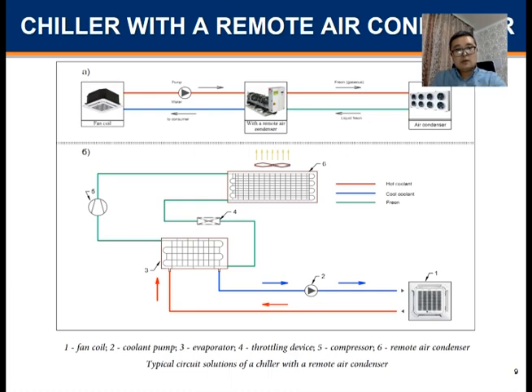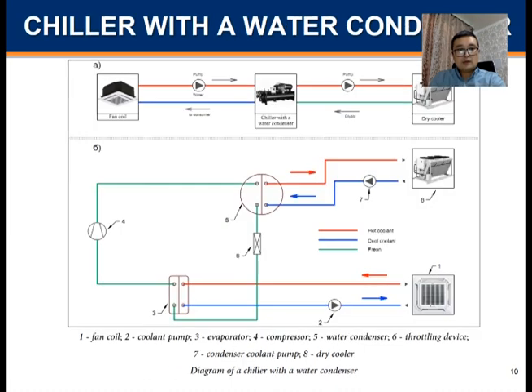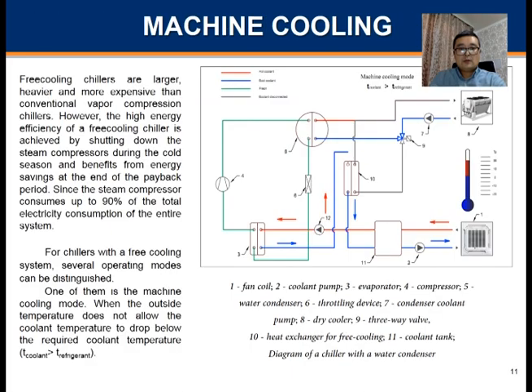Free cooling chillers are larger, heavier, and more expensive than conventional vapor compression chillers. However, the high energy efficiency of a free cooling chiller is achieved by shutting down the steam compressors during the cold season, and it benefits from energy saving at the end of the payback period, since the steam compressor consumes up to 90% of the total electricity consumption of the entire system.